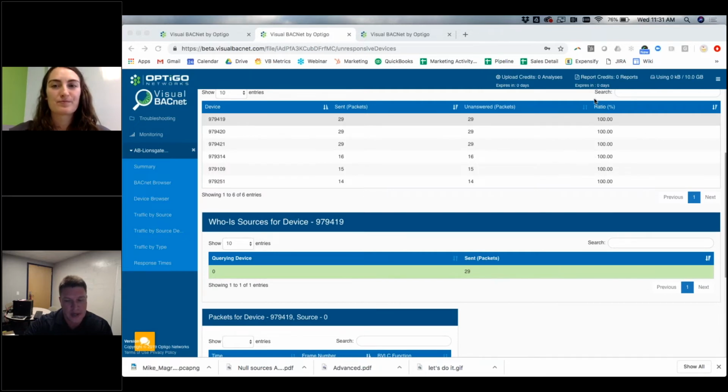We go down through, and all of a sudden we see the MSTP refresh rate is 200. That's 200 milliseconds on an MSTP trunk. There's no sense in us really troubleshooting it. There's physical wiring problems, or there's too many devices chatting on that network for it to operate properly. Right. So there's a mechanical element to that we have to analyze and say, yeah, we're going to have to go do a capture, and I'm actually scheduling to go out to that site this next coming week so that I can do a deeper dive and take a look at the wiring, look at cabinets.